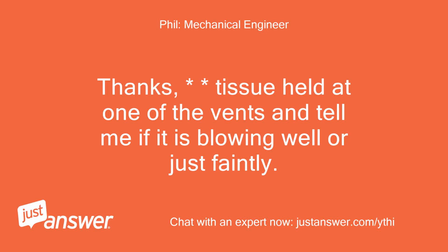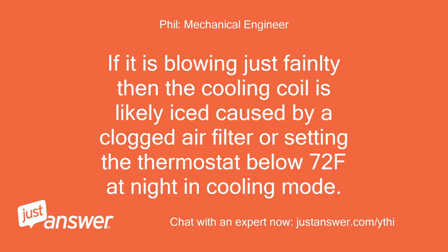Thanks. Hold tissue at one of the vents and tell me if it is blowing well or just faintly. If it is blowing just faintly, then the cooling coil is likely iced, caused by a clogged air filter or setting the thermostat below 72°F at night in cooling mode.